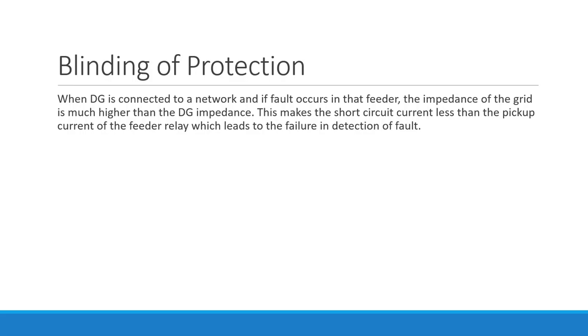Blinding of protection. When a DG is connected to a network and a fault occurs in that feeder, the impedance of the grid is much higher than the actual DG impedance. So what would happen as a result? This makes the short circuit current less than the pickup current of the feeder relay. Consequently, it is going to lead to failure in detection of the fault. So this is called the blinding of protection. This is another issue with the protection of microgrid.